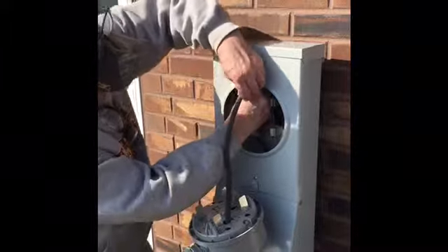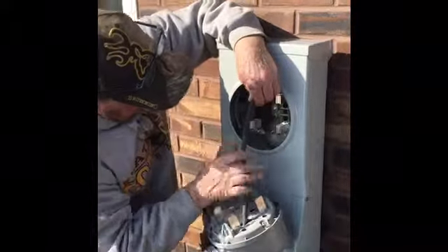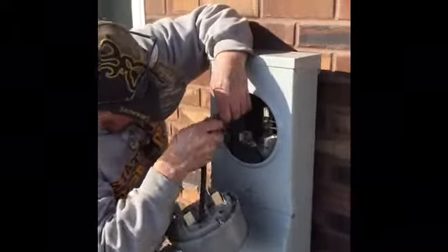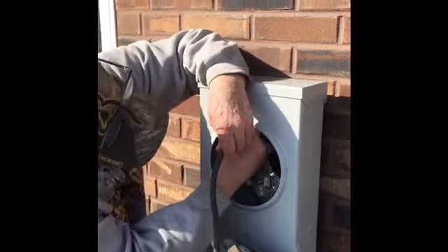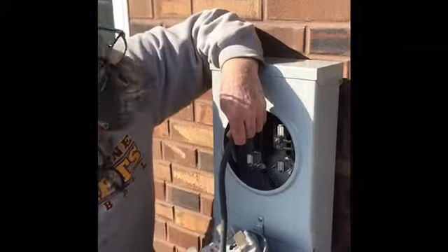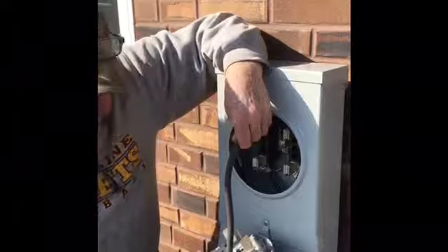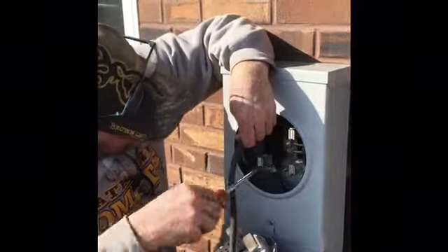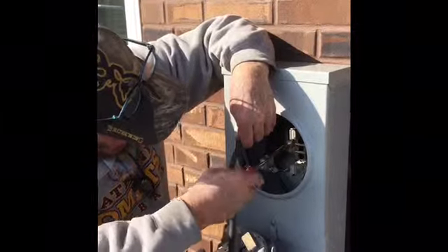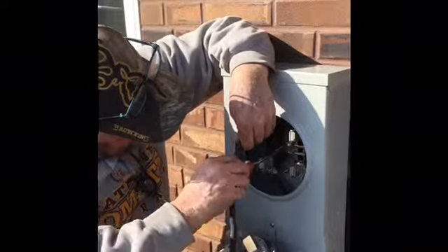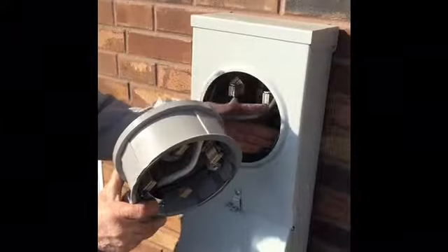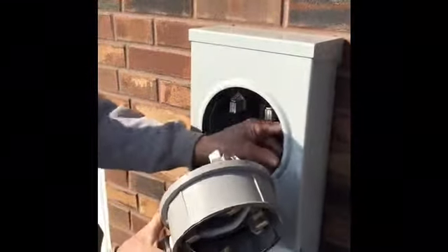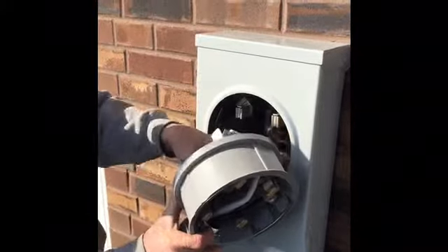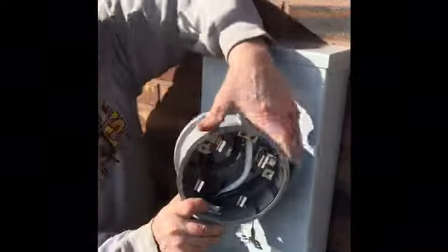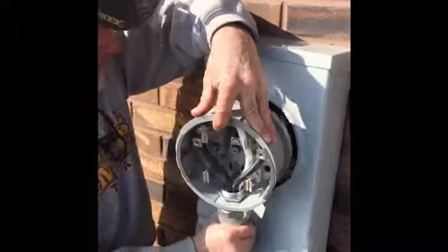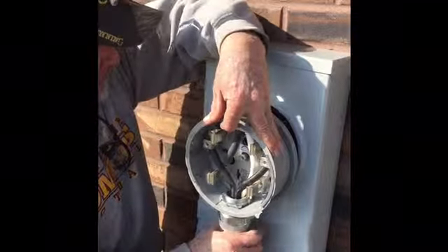Now this is a critical step to installing the unit properly, because a secure neutral is critical to the function of the auto transformer. It's critical to how it establishes the. So as you see, he's got it installed there. It's critical that it's installed properly to make sure that we don't end up with burned up meter socket heads.